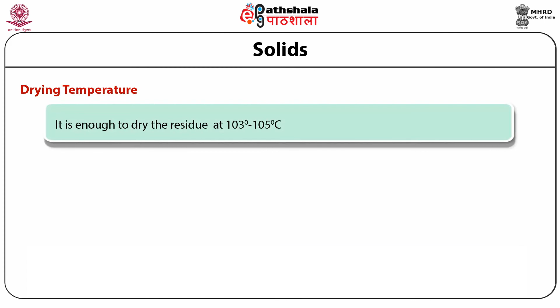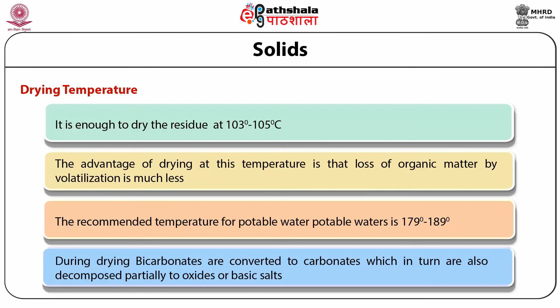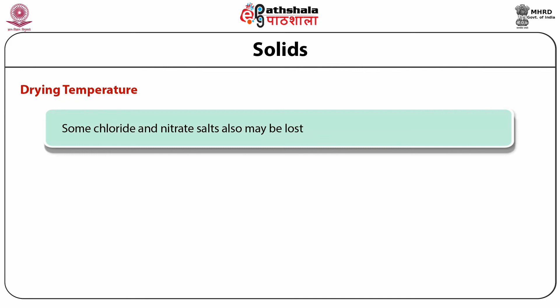Now we discuss the drying temperature. It is enough to dry the residue at 103 to 105 degrees centigrade. The advantage of drying at this temperature is that the loss of organic matter by volatilization is much less. The recommended temperature for potable water is 179 to 181 degrees centigrade, at which almost all the mechanically occluded water and most of the water of crystallization are removed. Organic matter is reduced by volatilization, though not completely destroyed. Bicarbonates are converted to carbonates, which in turn are partially decomposed to oxides or basic salts. Some chloride and nitrate salts may also be lost.